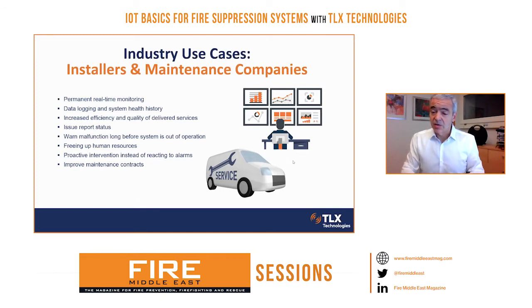Second, we've changed 2 interventions — we replaced 2 interventions with 1, because now the full data on what type of cylinder, what type of agent, and when it will go into alarm is available remotely. So the installer company can go in 1 intervention and fix a failure that otherwise would have taken a couple of visits to resolve, and a few days with the system out of operation.